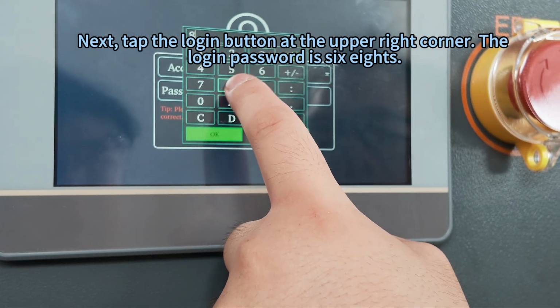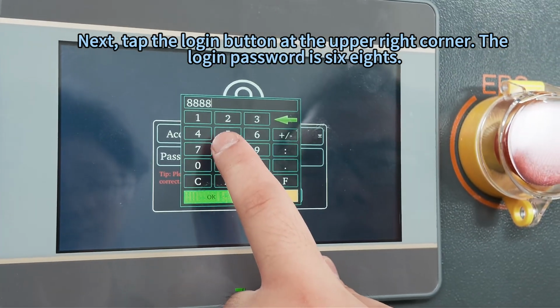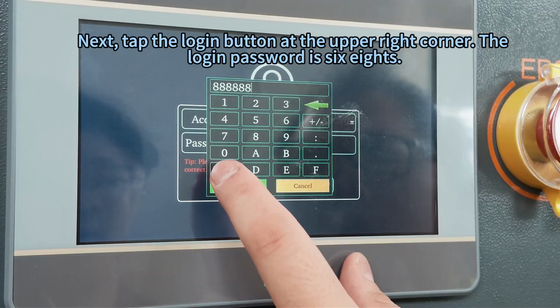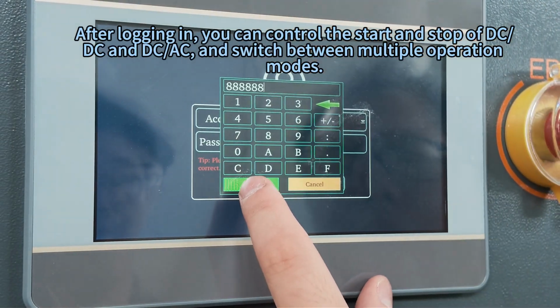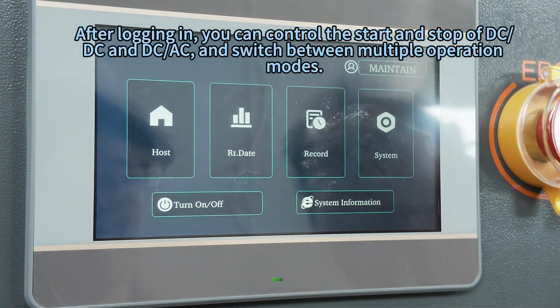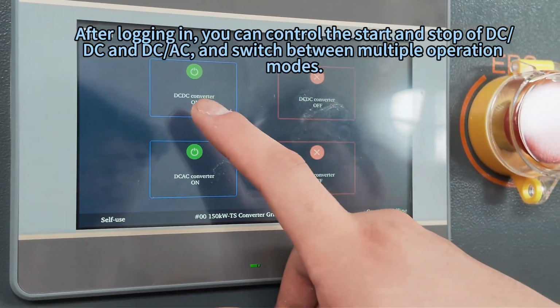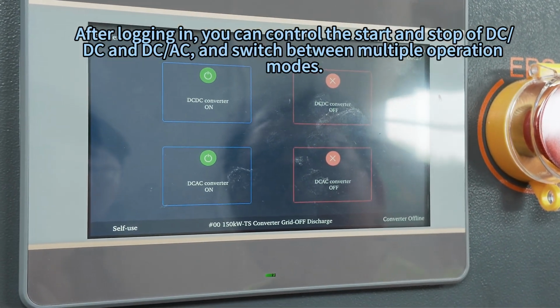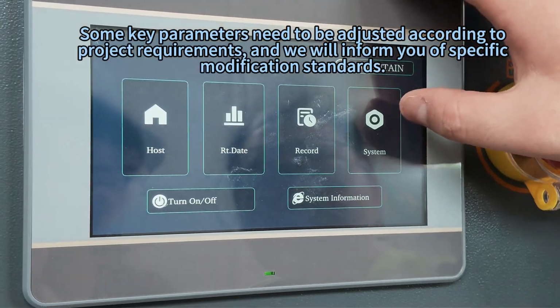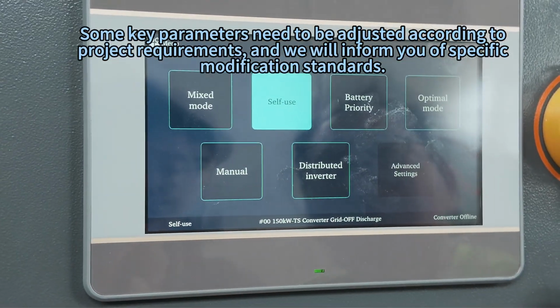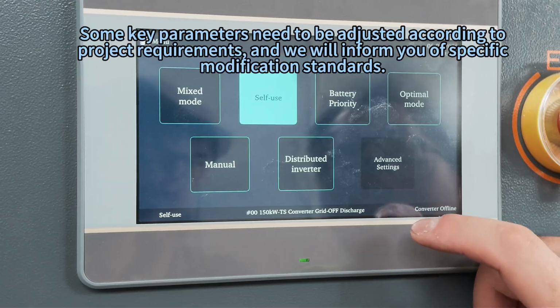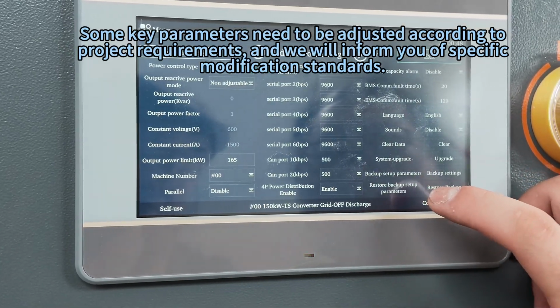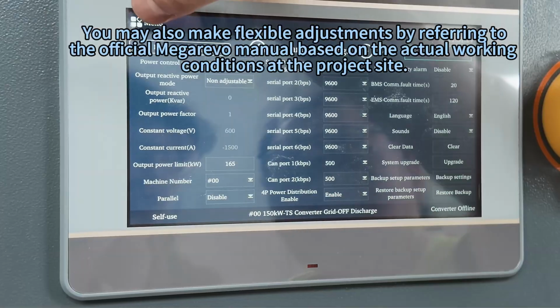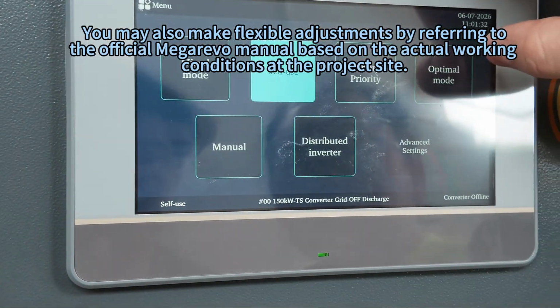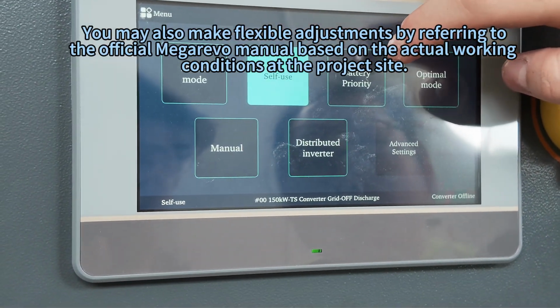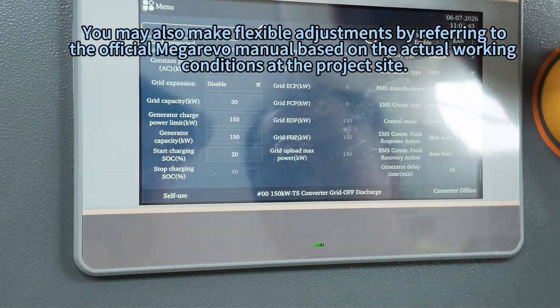Next, tap the login button at the upper right corner. The login password is six eights. After logging in, you can control the start and stop of DC, DC, and DC AC and switch between multiple operation modes. Some key parameters need to be adjusted according to project requirements, and we will inform you of specific modification standards. You may also make flexible adjustments by referring to the official Megarevo manual based on the actual working conditions at the project site.